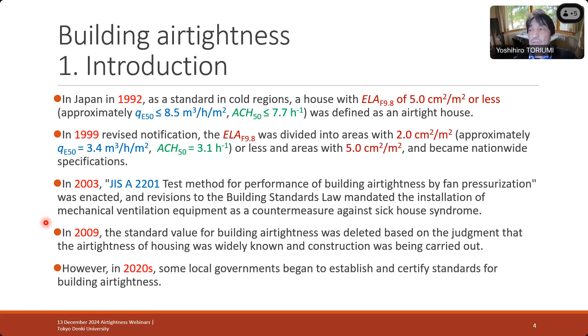In Japan, ELA F9.8 is used as an index of airtightness. ELA F9 is calculated by jointly establishing equation 1 and equation 2 with a pressure difference of 9.8 Pascal, and dividing the result by the floor area.